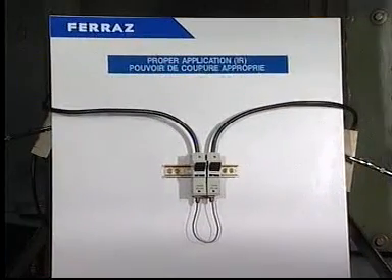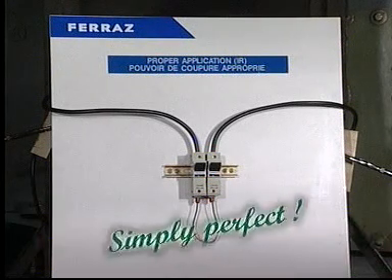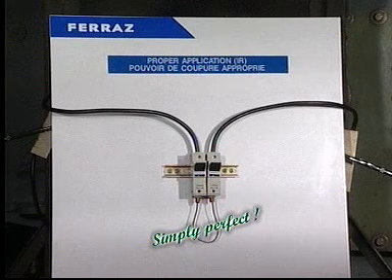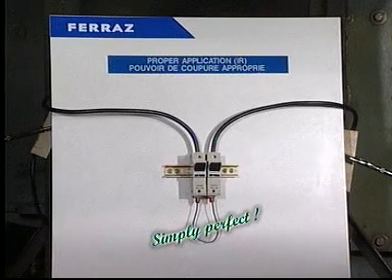The third and last test, with identical test parameters, employs current-limiting Class J time delay fuses. There is no damage to the small conductor, since the let-through energy was less than the withstandability of the conductor. The fuse's high level of current limitation provides superior thermal protection to conductors, thereby maximizing electrical system life.